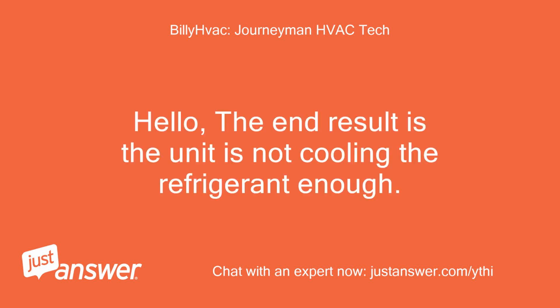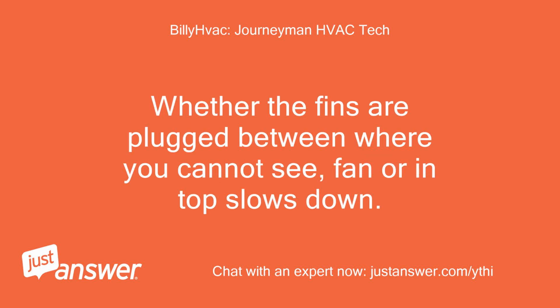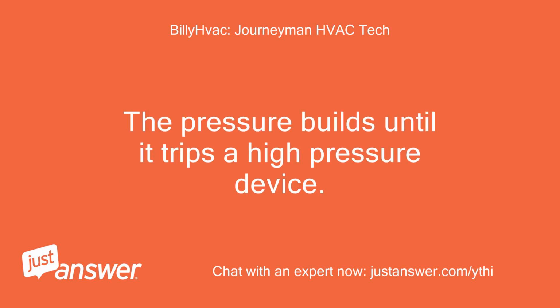Hello, the end result is that the unit is not cooling the refrigerant enough. Whether the fins are plugged where you cannot see, or the fan or top slows down, the pressure builds until it trips a high pressure device.